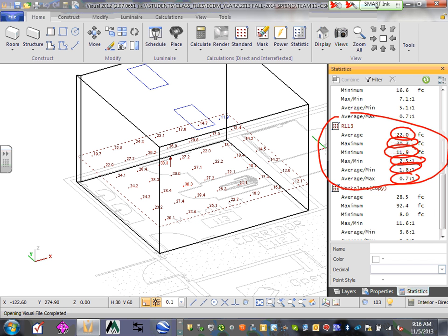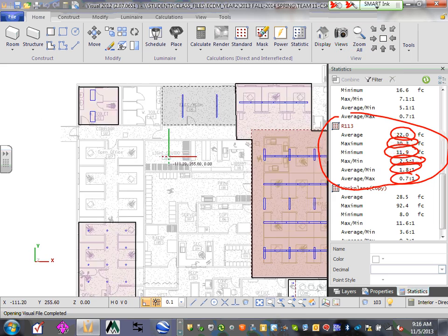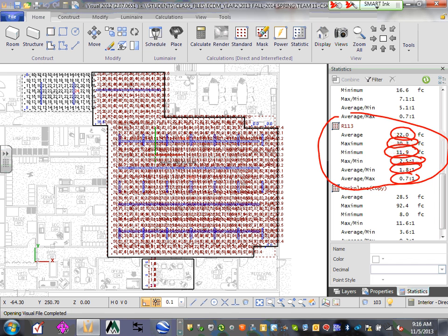When we finish with the calculation we export it to CAD, import it back into Revit, and lay out all the lighting fixtures. You put all your lighting fixtures in the space and then circuit them — typically 18 fixtures on a 120-volt 20-amp circuit because the volt-amps on them are less than 100. Then we put occupancy sensors and low voltage switches on them to turn them on and off.